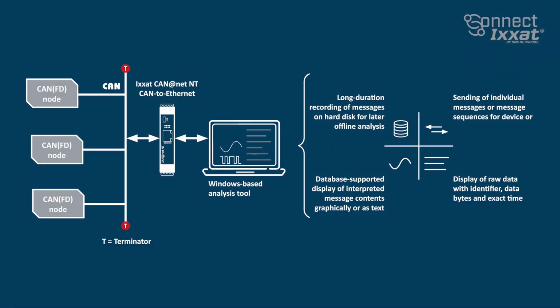When you have the CANnet in VCI mode attached to the network, you can continuously observe and log all the activities on the CAN networks, particularly looking out for error frames. This constant surveillance helps to quickly identify and diagnose any issues before they have a big impact and lead to a significant downtime. It's all about catching the errors as early as possible and addressing them promptly. This approach not only helps maintaining the stability of the network, but also significantly reduces the potential for prolonged disruptions that can arise from unresolved network issues.